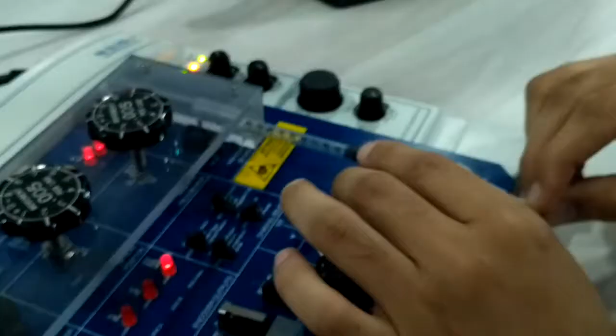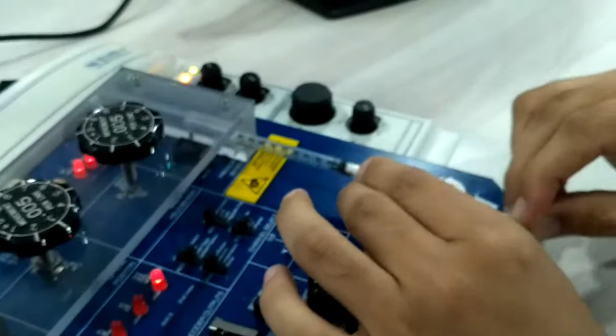Last of all, I move it to the complete end, the zero end for me, and I'm getting the maximum voltage out of this pressure sensor as 3.91 volt. You can also move it backwards and see the reading change, as it is being pressurized and unpressurized. This is how to take the readings.